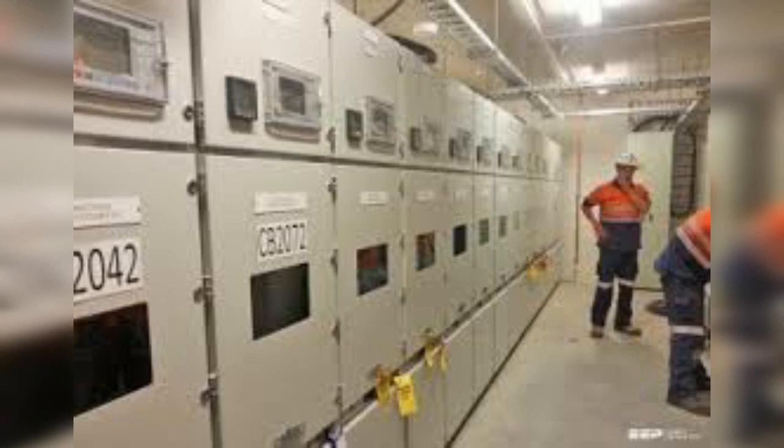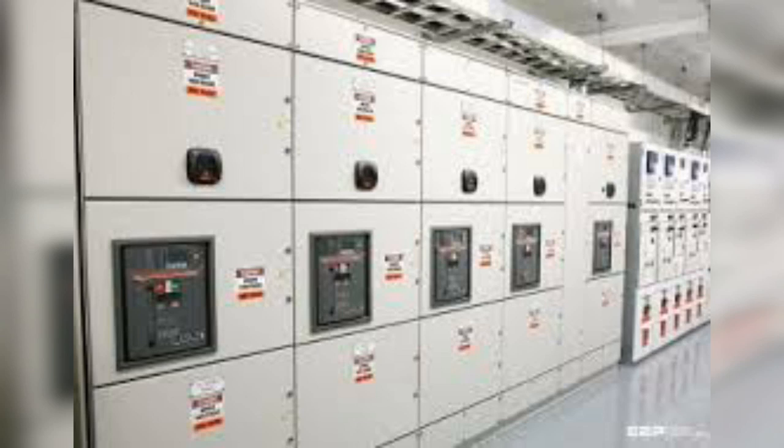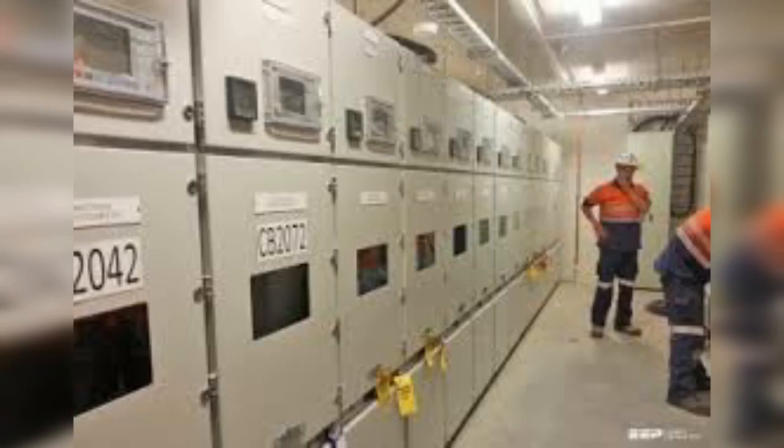In emergency cases, an automatic transfer switch is used to transfer the electrical supply without interruption, operated through an interlocking system, and a parallel operation will be done. In this auto system, some outgoing feeders of non-essential load will be disconnected to keep the power demand within the generator rating, which is mostly less than the rating of the utility source.